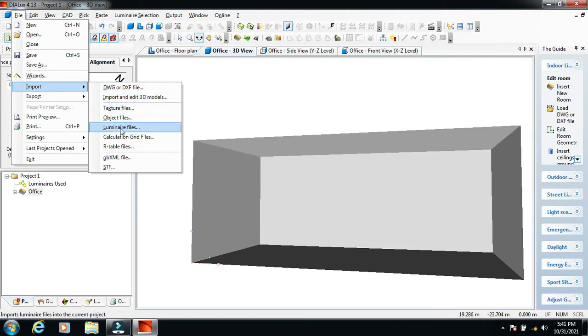Now as we do lighting, we have to import IES files. Each manufacturer has their IES file. IES stands for Illuminating Engineering Society, which is a governing body. Every particular light fixture has its own IES file. The details of the light fixture in terms of lumen output, size, dimension, and all other details will be incorporated in that file.